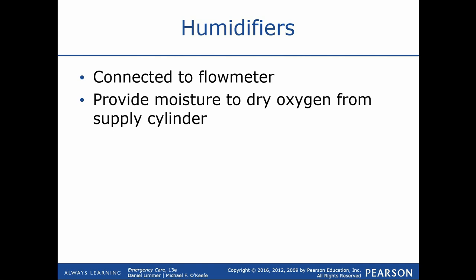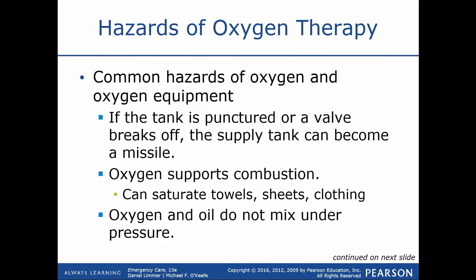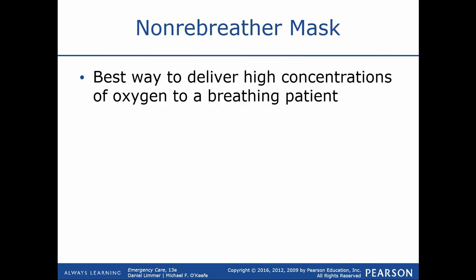From time to time you may be instructed to provide humidified oxygen, which can be delivered through a humidifying device or nebulizer using saline. A humidification bottle allows the oxygen to bubble through sterile water, mixing moisture into the air. That moisture is then carried along with the oxygen through the tubing and delivered to the patient, preventing the airway from drying out.